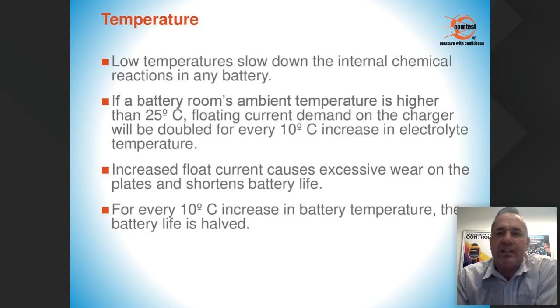So when we have all of those batteries on standby, we have a charger that is topping them up to keep them at the optimum charge level. So if the temperature rises, the floating current will need to be increased. The increase in your float current causes excessive wear on the plates and shortens your battery life. So there's a side effect on that. For every 10 degrees Celsius increase in battery temperature, the battery life is halved. So that's another consideration. These battery rooms where these racks are installed will need to be temperature controlled as well. So part of maintaining your batteries would also be the ventilation and the air conditioning.